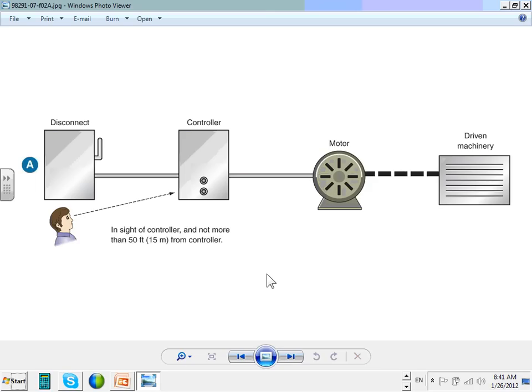With bigger motors, there's certain things that motors have to have. One thing is a disconnect. Everybody knows what a disconnect is for. We've been talking about disconnects, and we sized them last quarter, and we will continue sizing them next quarter. A disconnect is a safety factor. It's not meant to be a controller, to turn on and off. It's meant to push the button, the machine stops now, go turn it off, lock it, tag it, and go work on the equipment, you or any mechanical guy who needs to work on this equipment.